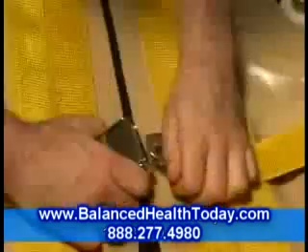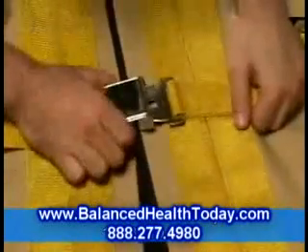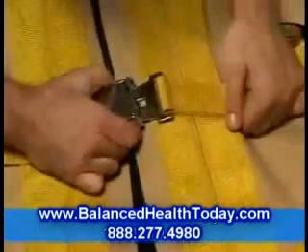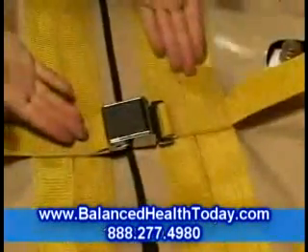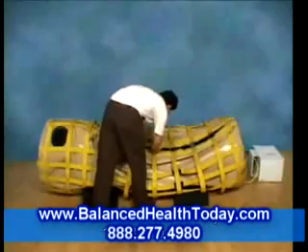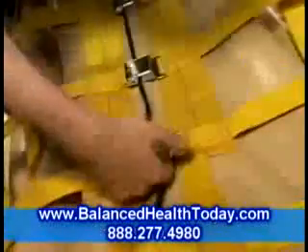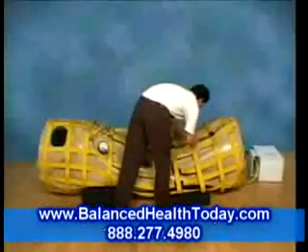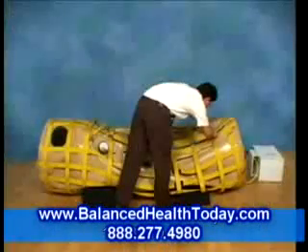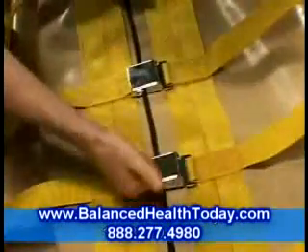Now let's buckle the chamber up. Close the buckles from the outside — one hand on the female buckle, the other hand on the yellow strap that attaches to the male buckle, then push the two together. Be sure to double-check all the buckles, as a click may not mean they are all the way closed. It's important to make sure all the buckles are properly closed or the chamber can be damaged.